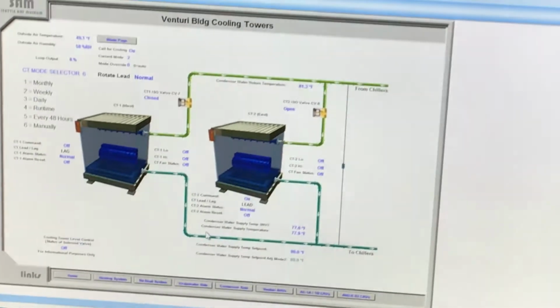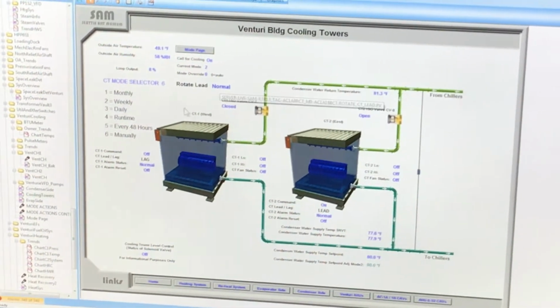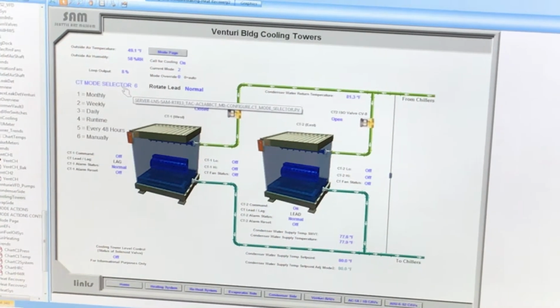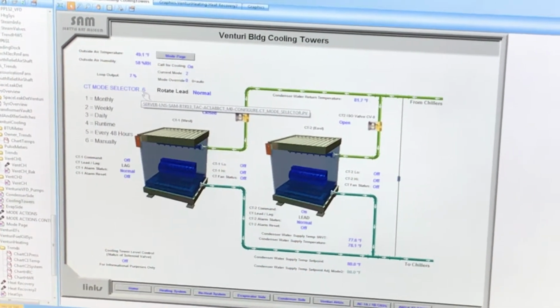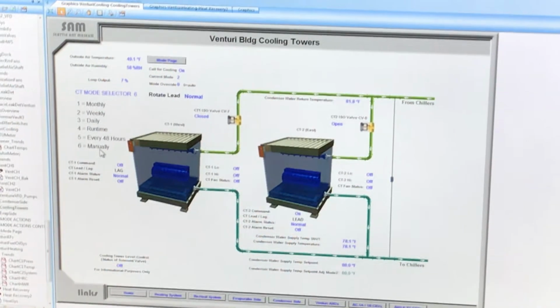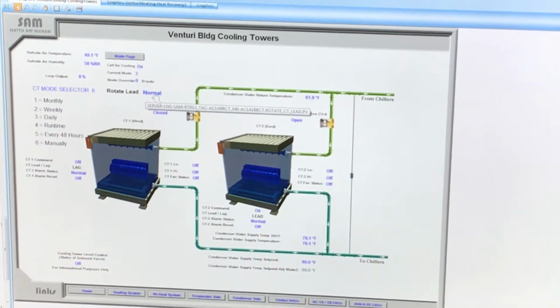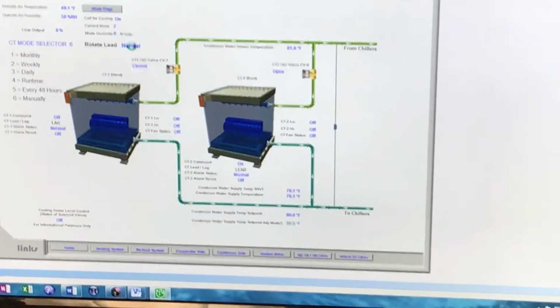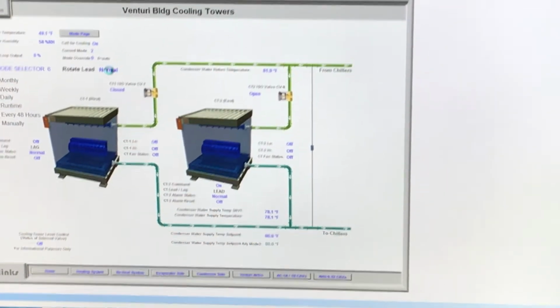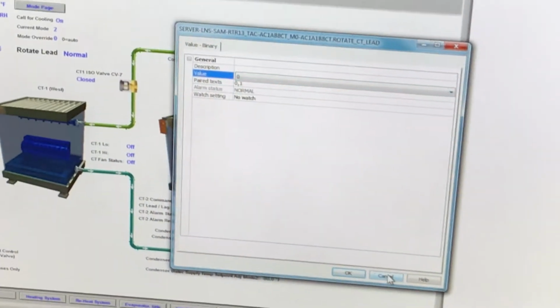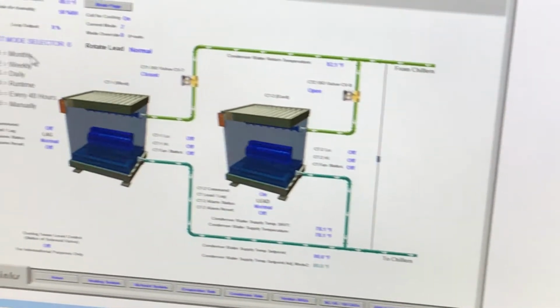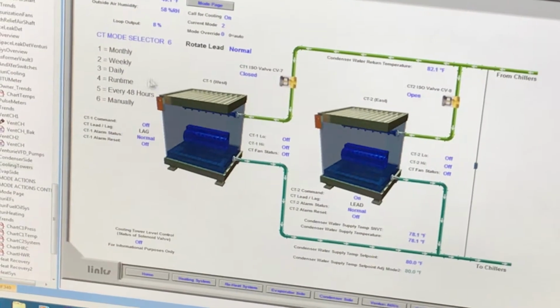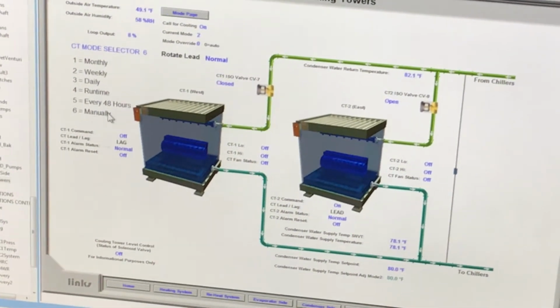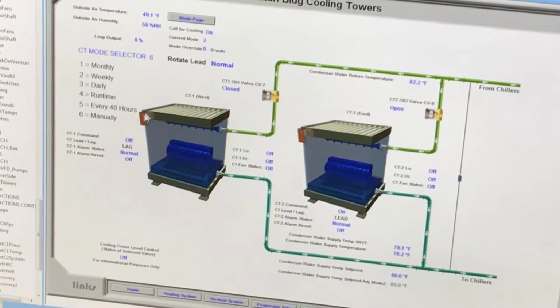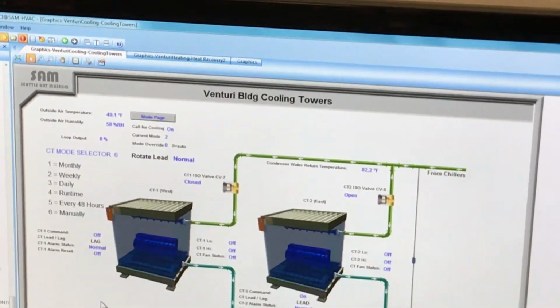You have right now the rotate lead at 6, which is manual. Yeah, for now, and it's normal right now. If you were to click that, you could rotate it. What is the number 1? We'll read them. Number 1 is monthly, 2 is weekly, 3 is daily, 4, I can't read that one. Runtime, every 48 hours. Normally we'll probably rotate them weekly.